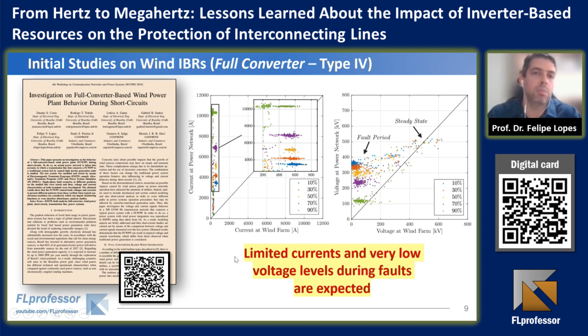Then, once we understood these aspects, we received the news that an IEEE report, released in 2018, was addressing the impact of IBRs on both power system dynamics and short circuit performance. Grid following technologies basically take the grid voltage information to synthesize currents that are injected into the system. They can basically be represented by a current source, and most of the early control schemes only inject positive sequence currents, suppressing the negative sequence currents and disregarding voltage support.